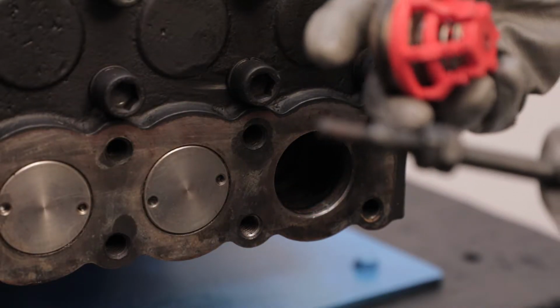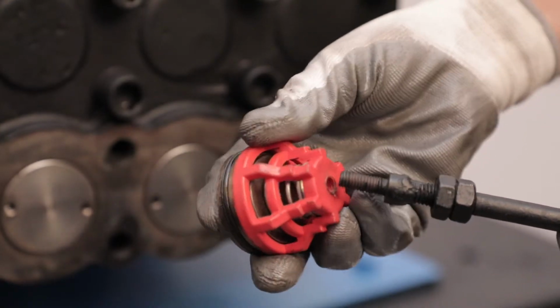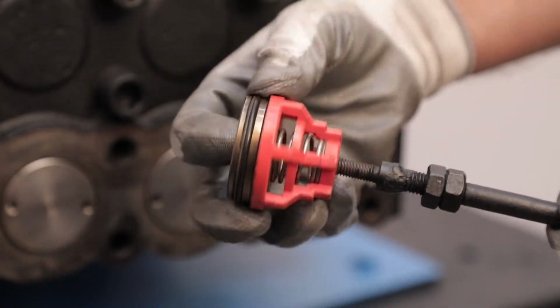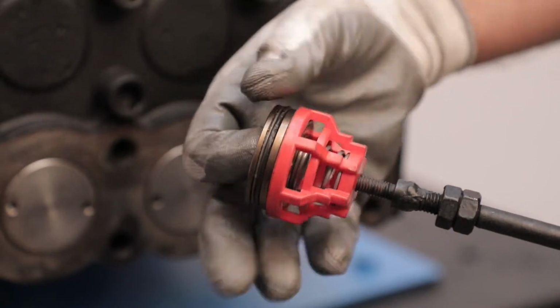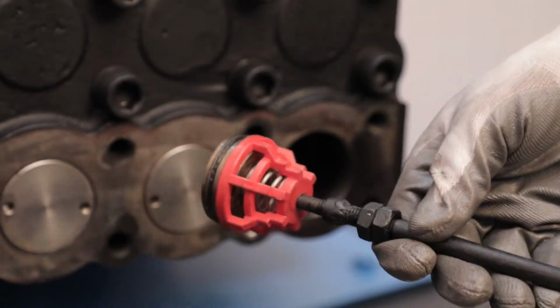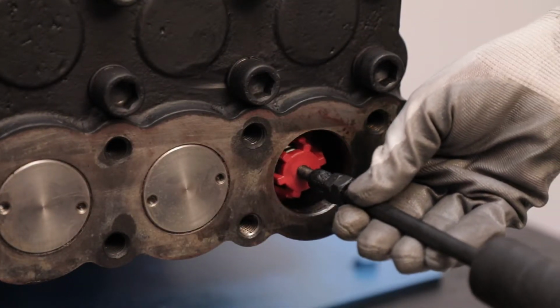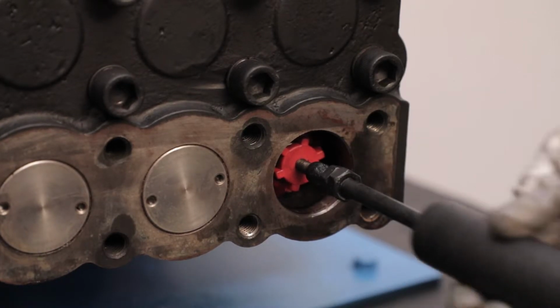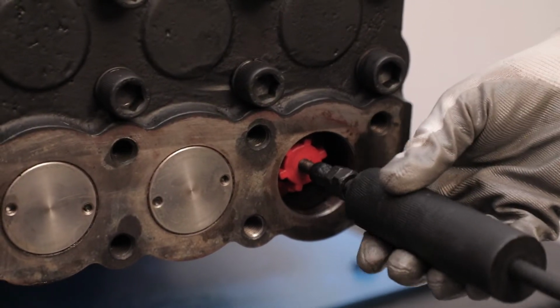Now, screw threads of valve puller into suction and discharge valve guide. Place and push valve assembly into pump head with the help of valve puller.